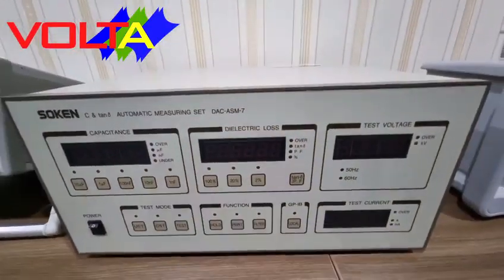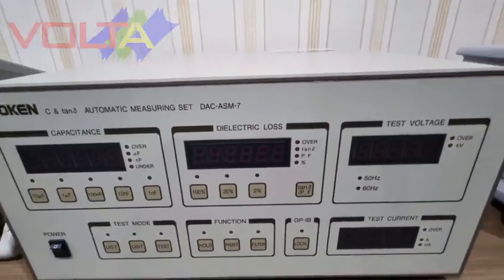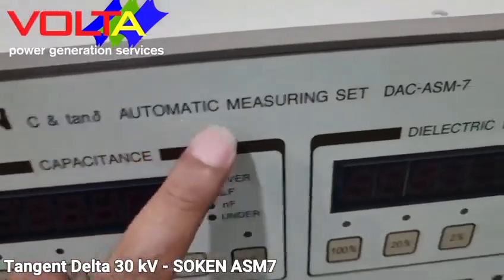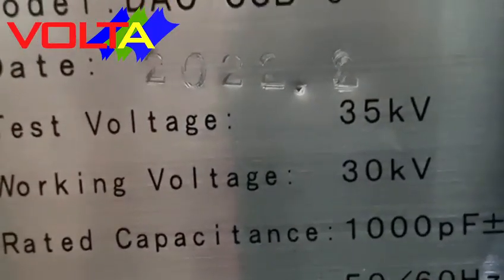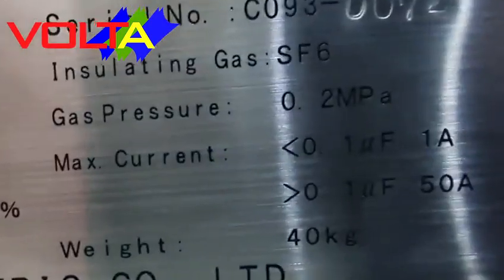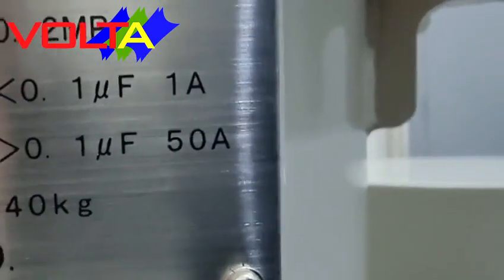For power factor tangent delta testing — to analyze the loss tangent of insulation — we provide two tangent delta test instruments. The first is the Soken DAC-ASM-7, provided with CX SF6 gas insulated standard, able to test tangent delta up to 30 kilovolts. For test objects with insulation capacitance more than 0.1 microfarad (100 nanofarad), it is able to test up to 50 amperes, and for capacitance less than 100 nanofarad, up to 1 ampere.